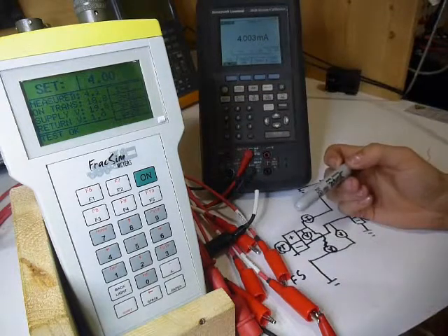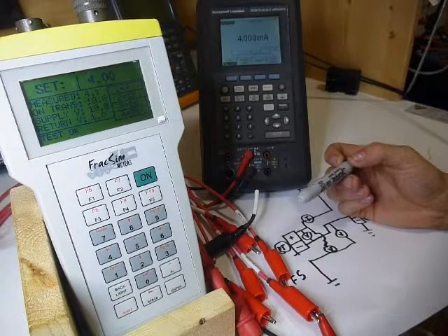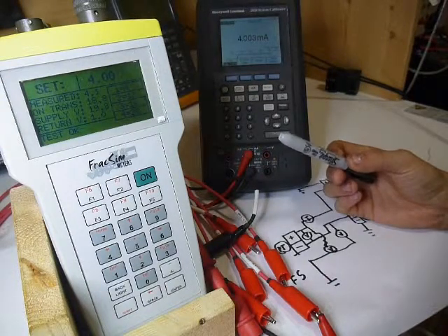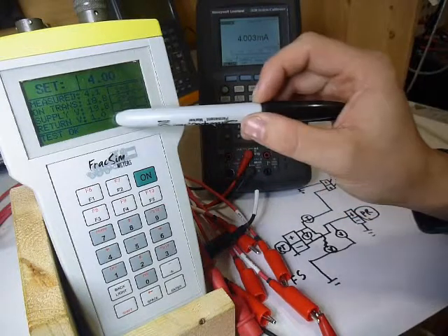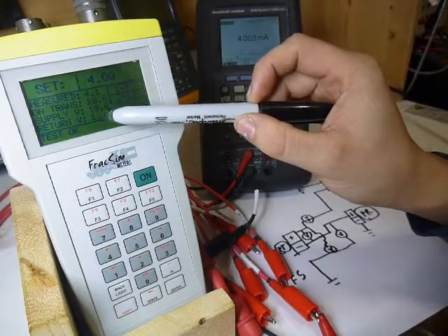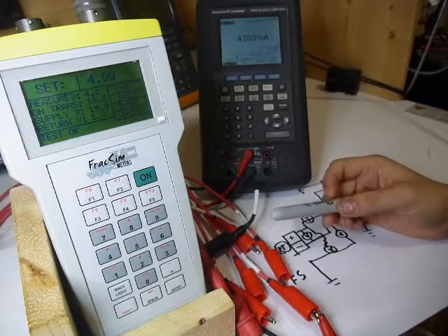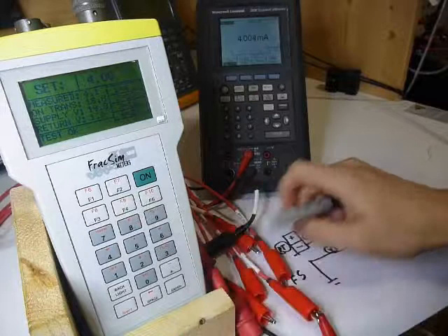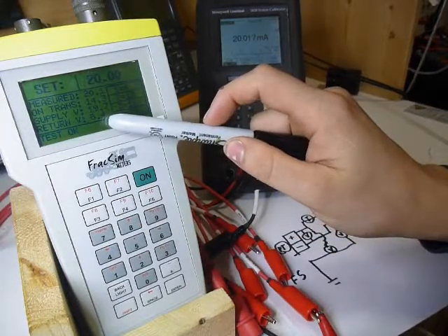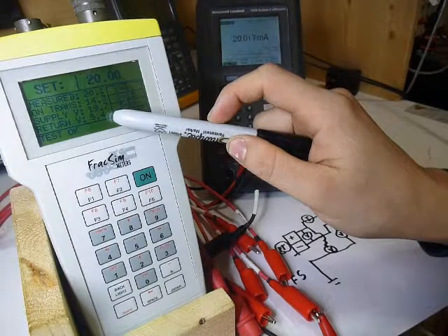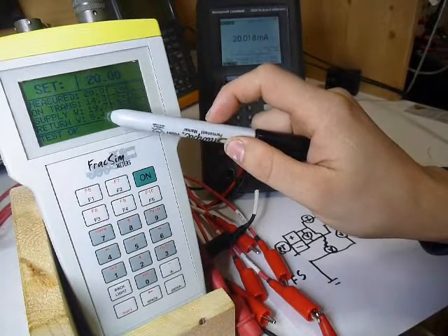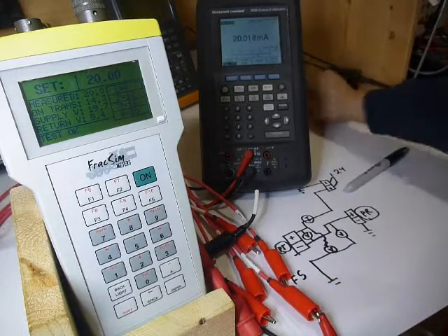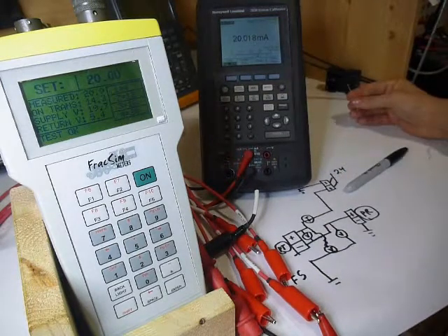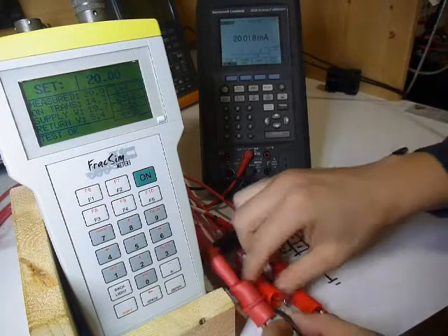So everything looks good. If you actually had a system that you knew the return resistance on, for example, most instrumentation systems, the older systems use a 250 ohm resistor, then you'd be able to tell just by looking at this return voltage and the current whether everything was working okay. And if I go to 20 milliamps, that should be 5 volts. See, it's 5.4, so it's a little bit out, but it's still within an acceptable level. I'm just going to put in there to demonstrate a possible failure, a 1k ohm resistor. Go back to 4 milliamps, of course.